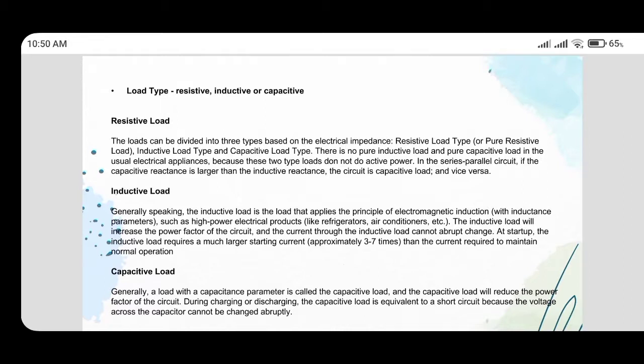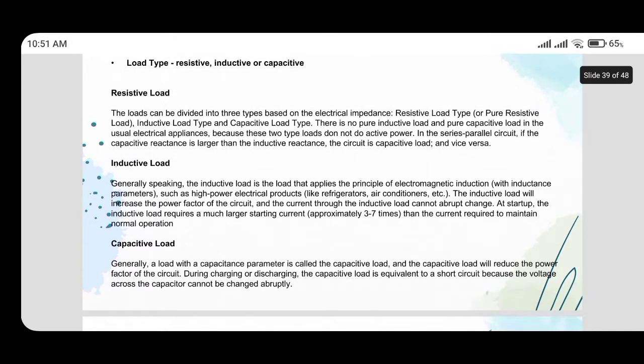Inductive load. Generally speaking, the inductive load is the load that applies the principle of electromagnetic induction with inductance parameters, such as high power electrical products like refrigerators, air conditioners, and so on. The inductive load will reduce the power factor of the circuit, and the current through the inductive load cannot change abruptly. At start, the inductive load requires a much larger starting current, approximately 3 to 7 times the current required to maintain normal operation.